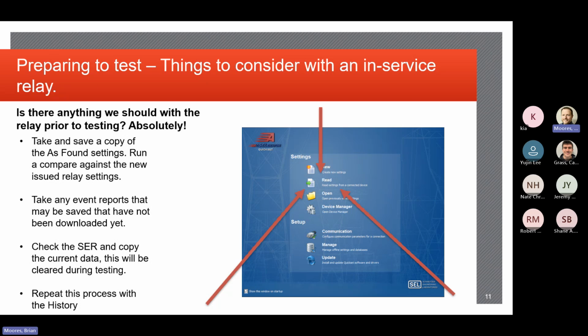But when you sit down as the test engineer, you're going to sit in front of that relay after you've got it all isolated and you've done all your due diligence. You're going to connect to that relay with your communication cable or your Ethernet cable. And the very first thing you're going to do is save a copy of the settings that are sitting in that relay as you found them.